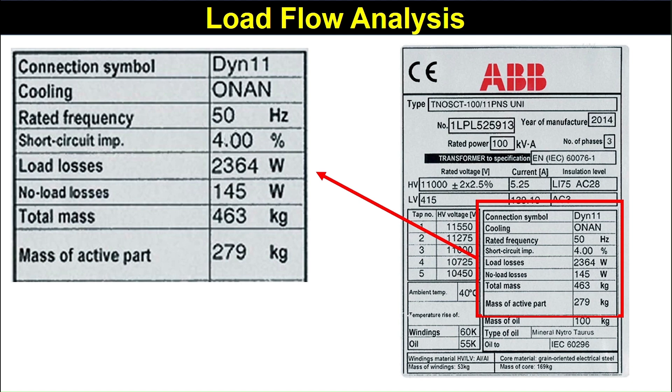No load losses, that is the no load loss is 145 watt and load losses, that is total losses, 2364 watt and short circuit impedance, that is the percentage impedance is 4%. These things are mentioned in the nameplate of the transformer.